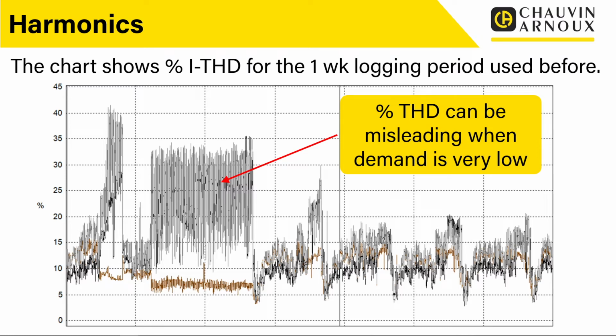So just be aware of that when you are monitoring these things, particularly if you're just measuring, say, with a harmonic clamp, and you're just measuring percentage THD. Just be aware that it does depend on the load on the circuits, the percentage content. So percentages can be a little bit misleading.